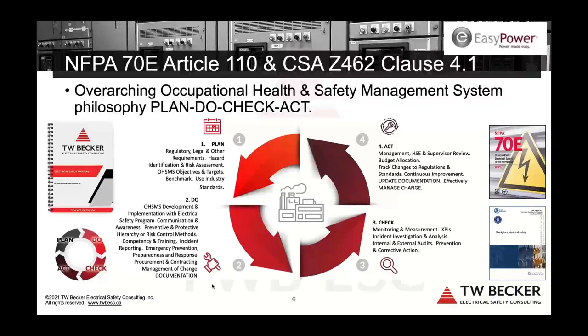And then we need some documentation filled out, because ultimately the supervisor should check. The supervisor needs to check. And this is also in 70E and Z462, the element of audit and field checking, field auditing by the supervisor. A documented job safety plan will allow the supervisor to do that, and it's a key component of this energized electrical job workflow. And if the workers aren't filling out the documentation correctly, then you work with them and coach them and get them to understand why the document is important to them, and that they take the time to fill it out.